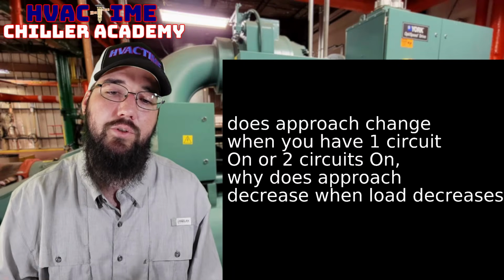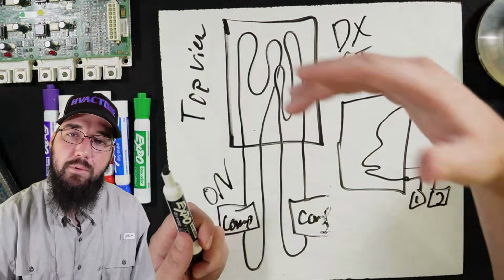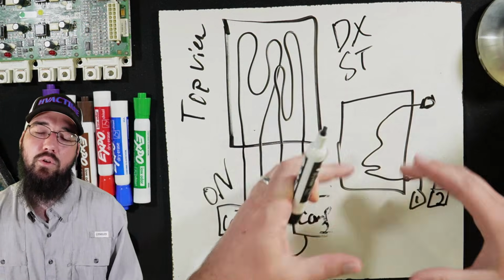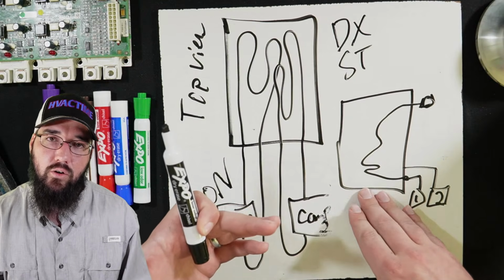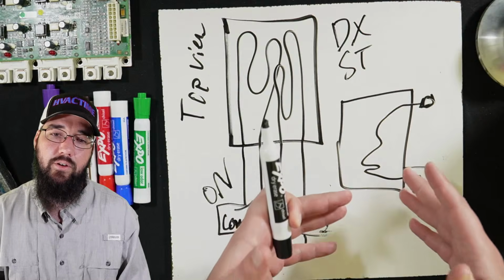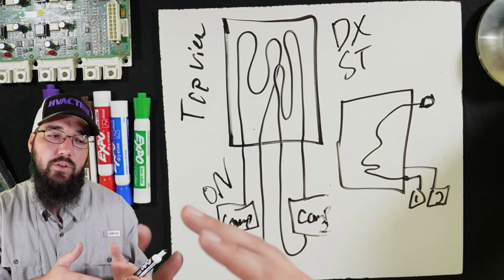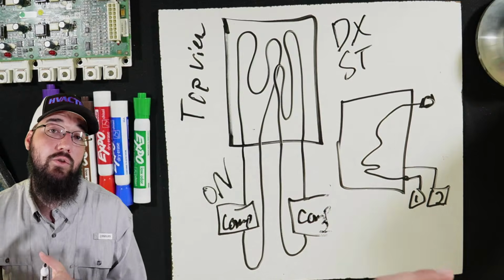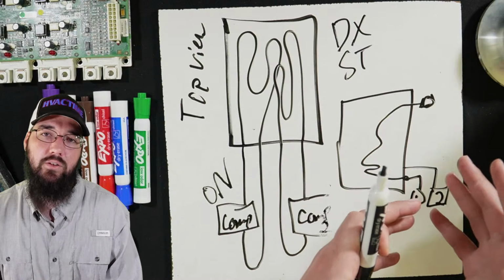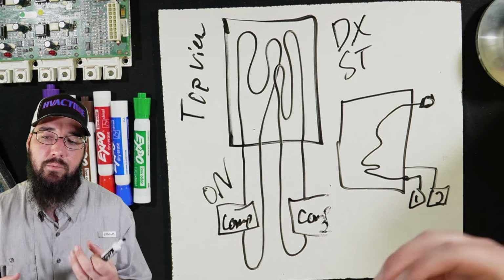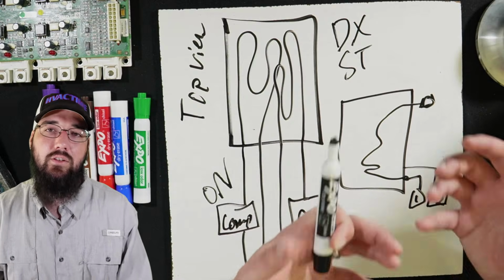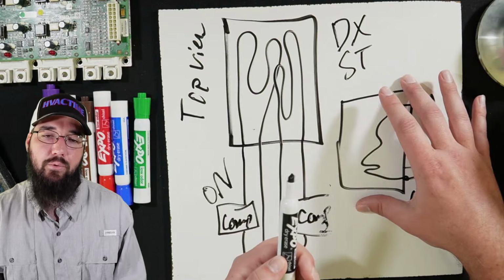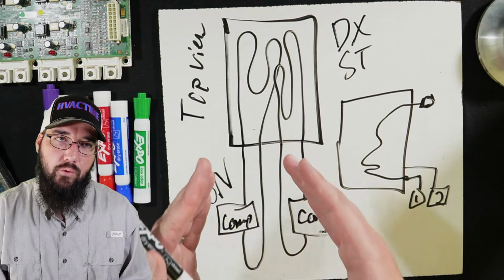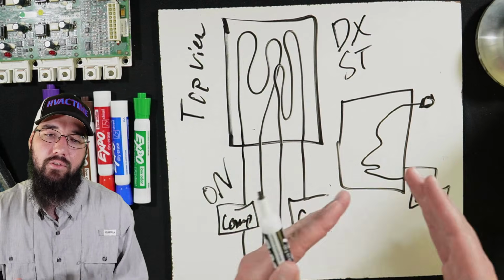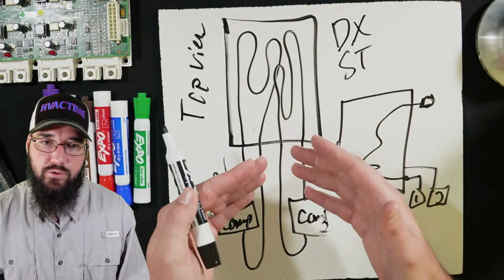This gets into the second phase of this question: why does approach increase or decrease with load? Keep in mind, we use a different version of approach when we think of air over coils or DX coils, direct expansion like this with an evaporator, because we think of it as, what is my return air to saturation, and then what is my saturation to supply air? But most of the time I'm thinking, what is my return air to my saturation temperature? That's what I spend the most time analyzing for a DX evaporator, air over evaporator. But in the water hydronic evaporator, instead of an air over, we refer to it as an approach value.